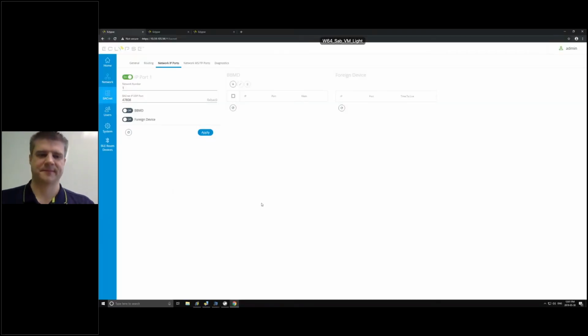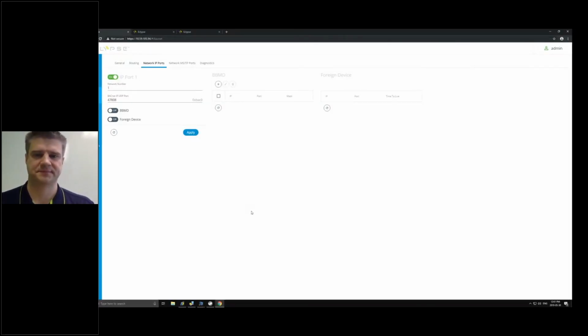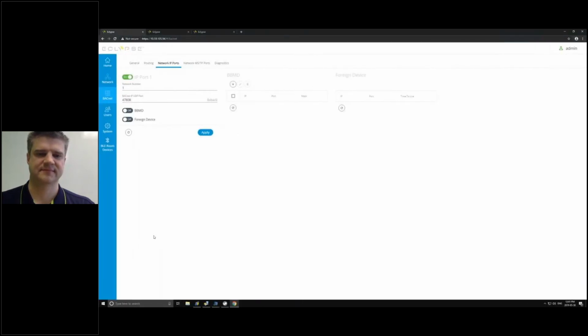As a live demo, we set up 3 Eclipse controllers: an S1000, a 303, and a VAV. We set them up all on the same network. Network IP, BACnet network port, network 1, port 47808. Because we're on the same network, we don't need to enable anything for BBMD.